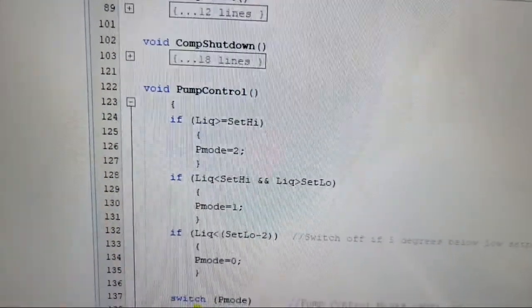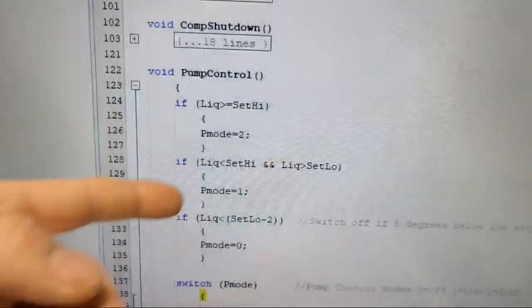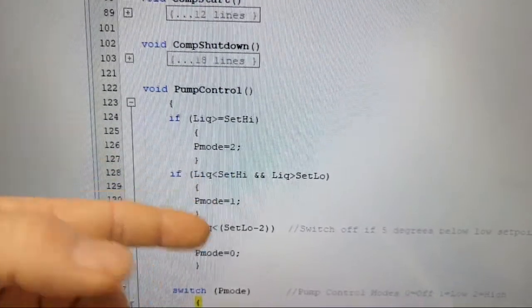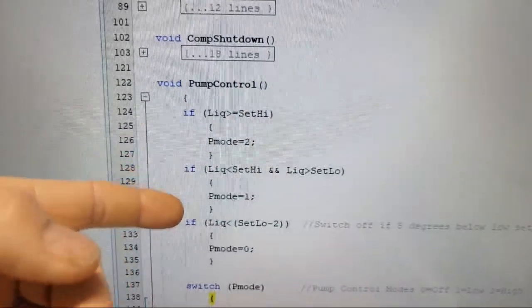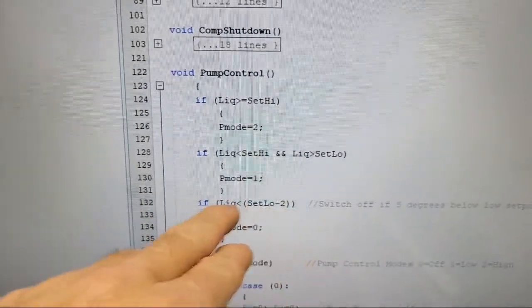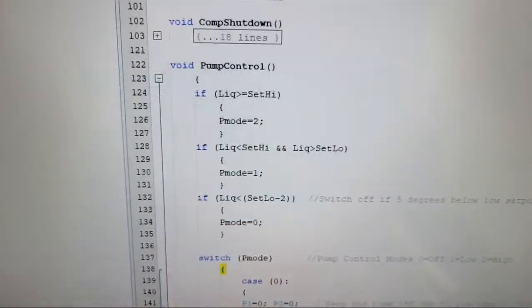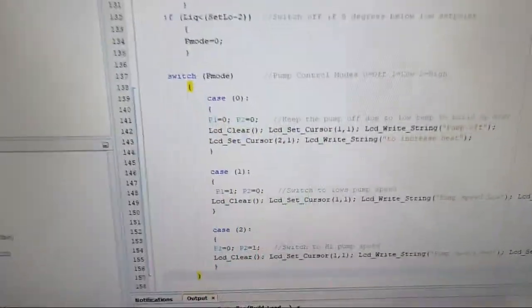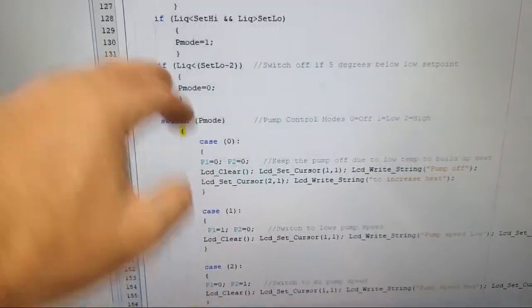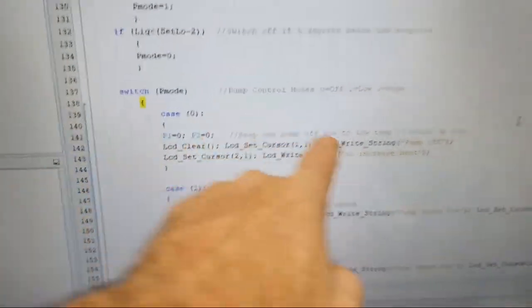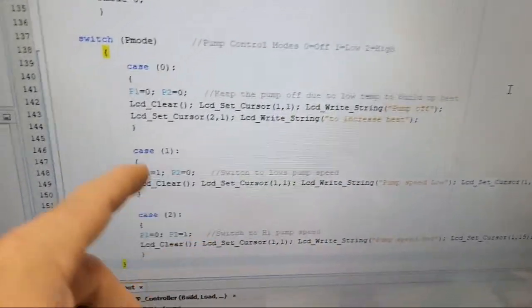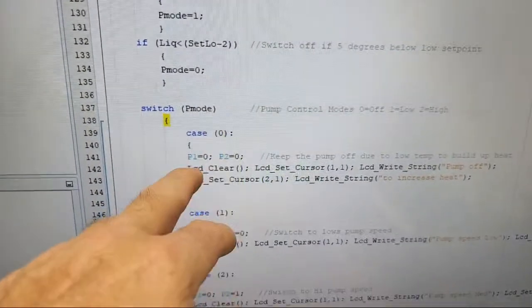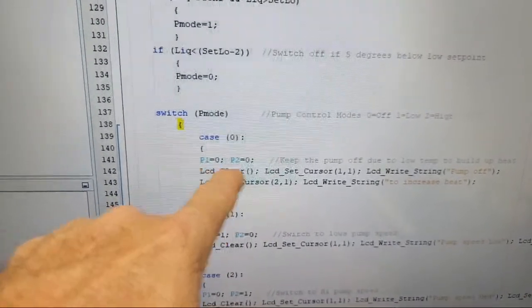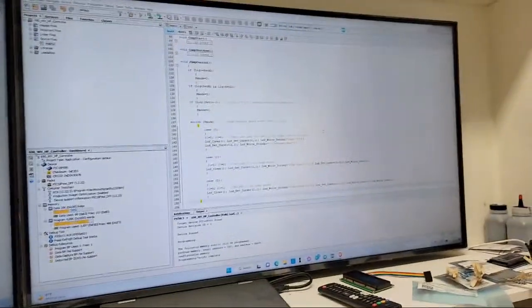If the thermistor is higher than the high set point, if you have 2 set points, then it's in high speed mode, basically pump mode 2. If it's between those ranges, it's going to be in mode 1, which is just the low speed. And if it's below the set point minus that differential, it's going to be off again. Then there are 3 cases basically, which is how it breaks up. It's going to display what's going on, and it's also going to control my assigned outputs on the microprocessor, P1 and P2, which are the outputs on the thing.